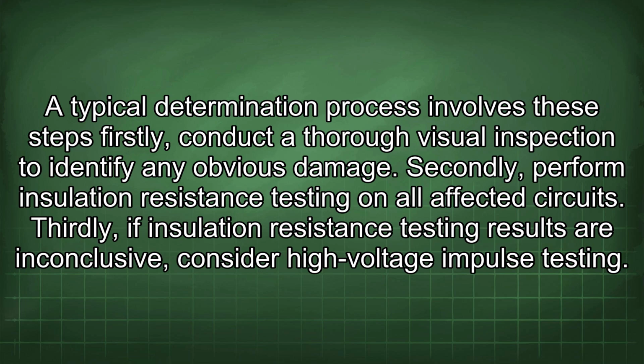Firstly, conduct a thorough visual inspection to identify any obvious damage. Secondly, perform insulation resistance testing on all affected circuits. Thirdly, if insulation resistance testing results are inconclusive, consider high voltage impulse testing.